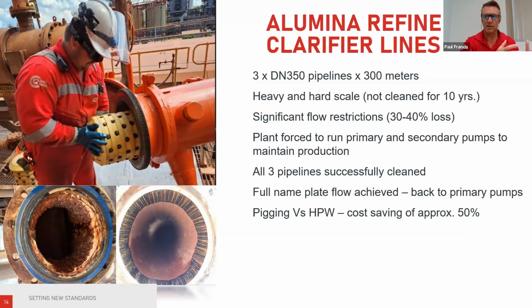If we'd done it earlier, we wouldn't have had that production impact, because we could have taken a line offline in a secondary state instead. As you can imagine, the pumps running these pipelines were all running flat out, which they shouldn't have been — they should have been running at about half capacity, but they were at full capacity, causing significant flow restriction of about 30 to 40% loss.